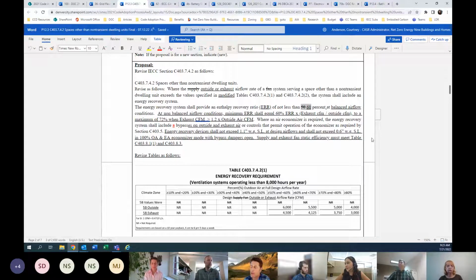because with energy recovery, if you don't have as much air going out, it's much harder to do the enthalpy recovery ratio. So we clarify that, and then we actually put in a factor that if you have unbalanced airflows, you can adjust the enthalpy recovery ratio, which is not the case currently. And I can get into a lot of that minutia. I think we've talked about it in this a few times, so I think everybody's understanding that.